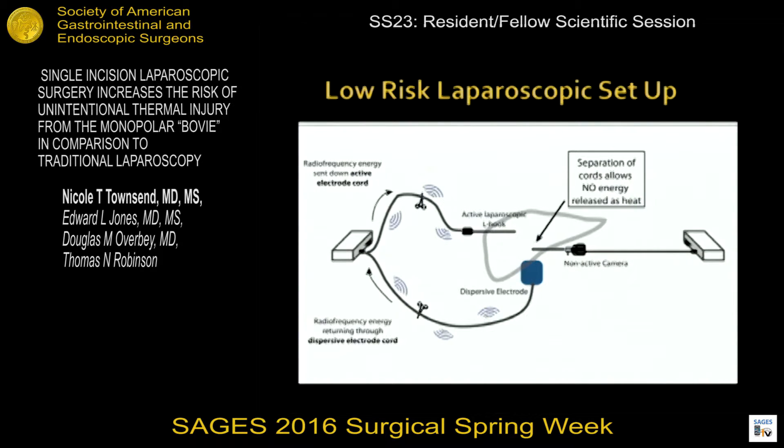Our previous data has demonstrated that there are several ways to mitigate the effect of this stray energy capture. This includes changing the power settings from 30 to 20 or 15, using cut mode instead of coagulation mode, decreasing the dwell time or active use of pressing the button on your monopolar instrument, and most importantly, separating the power generator from the camera power source, which prevents the cords from aligning in a parallel fashion and eliminates the opportunity for antenna coupling and stray energy capture.